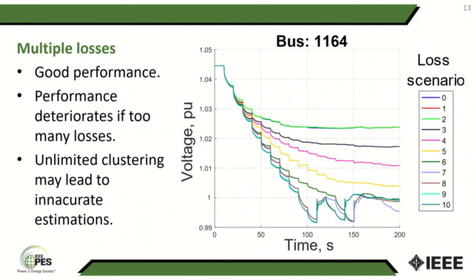Moving on, we have the case for multiple simultaneous losses of voltage meters. Notice the controller is able to cope with up to 2 simultaneous losses and still be able to control the voltages as in the original case with full measurements. Observe how reducing the pool of measurements to conduct the estimation deteriorates the performance of the controller as it reduces its visibility. The system does not become unstable as the controller is very robust. However, unnecessary control actions are undertaken if the quality of estimations is left unchecked.